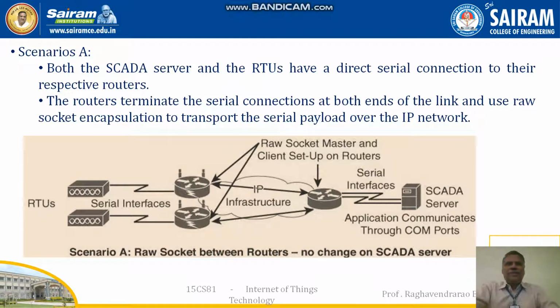In scenario A, if you consider a raw socket between routers, there is no change in the SCADA server. Both the SCADA server and RTUs have a direct serial connection to their respective routers. So the router terminates the serial connection at both ends of the same link and uses raw socket encapsulation to transport the serial payload over the IP network.